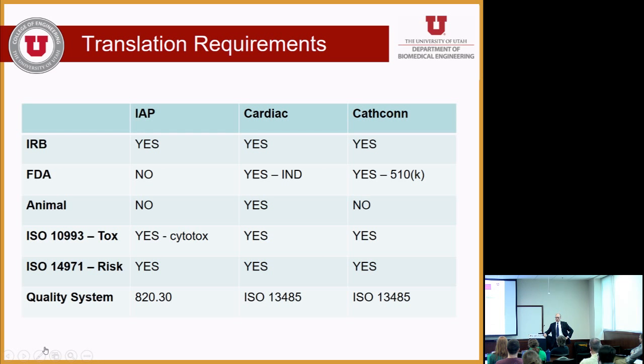A much easier way is through a 510K. And so a 510K is your application to the FDA to show that you're substantially equivalent to a predicate device that was made before 1976. And so it's a bit of a loophole. It's a bit of a loophole that people have become very good at exploiting in order to get their devices into the marketplace. But clearly, if you're going to make a new bedpan, should you have a full scientific review of your data and your manufacturing? Probably not. But a bedpan is a medical device, so is a tongue depressor.